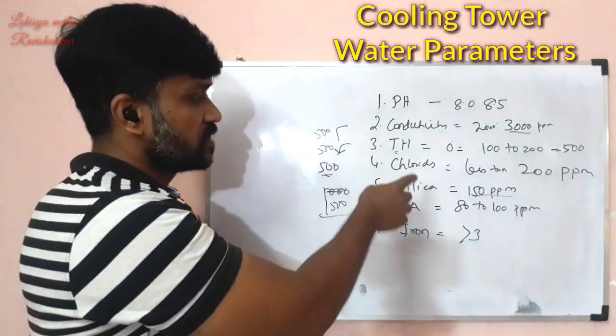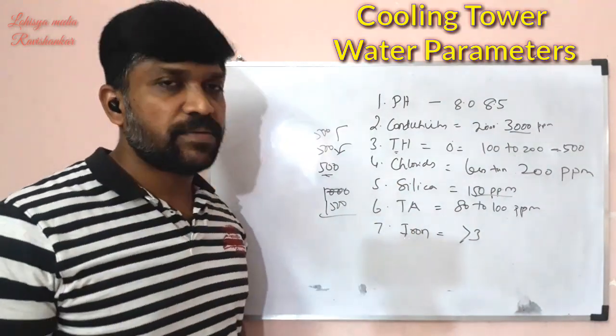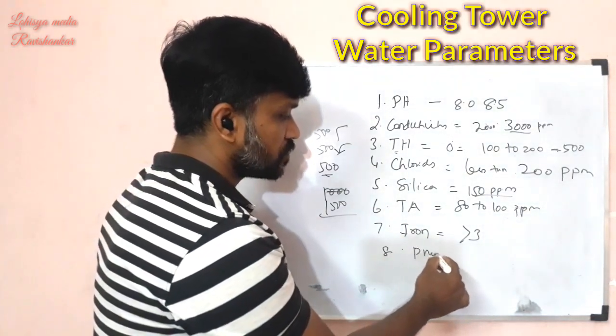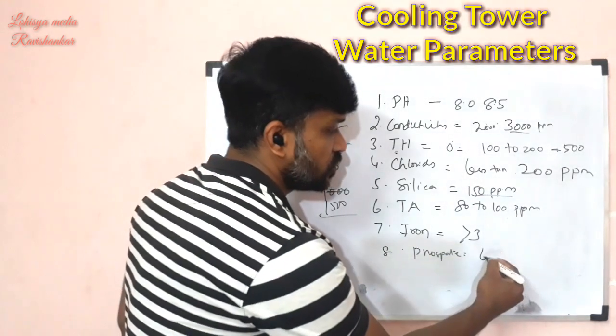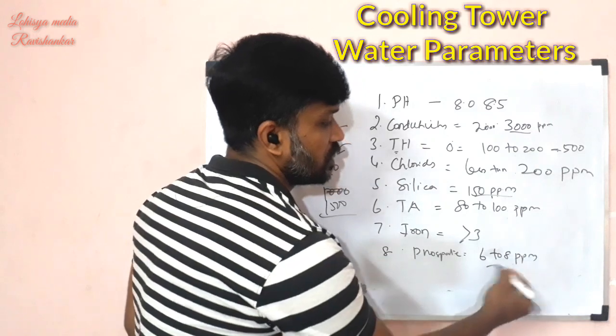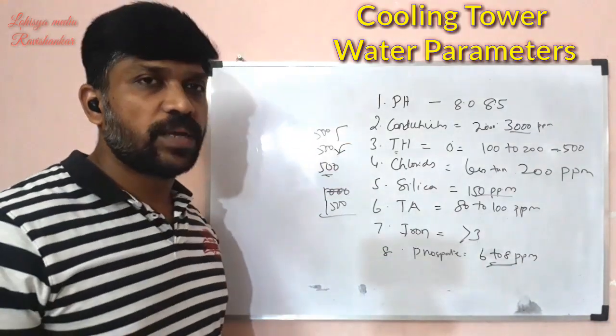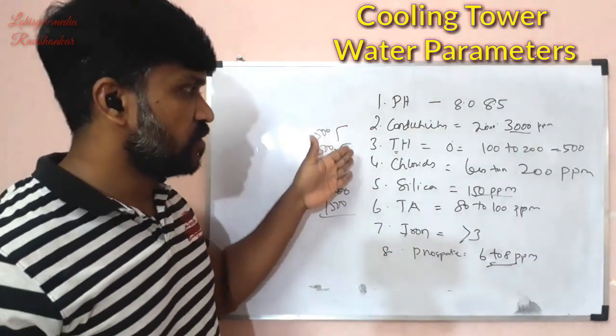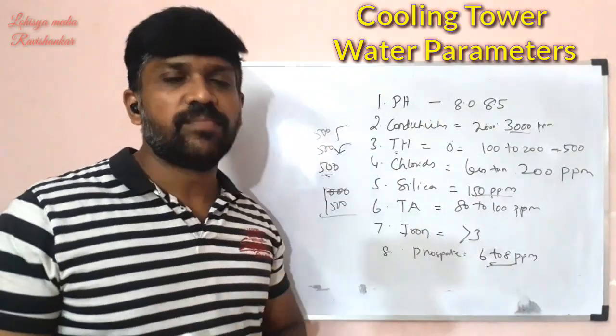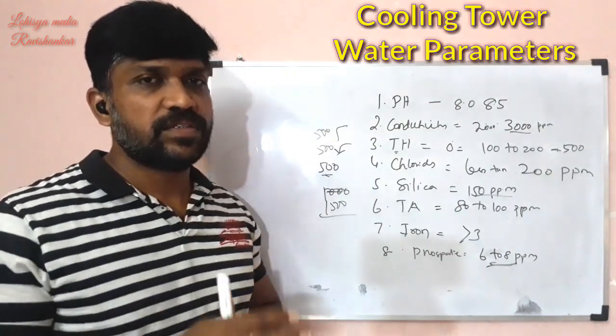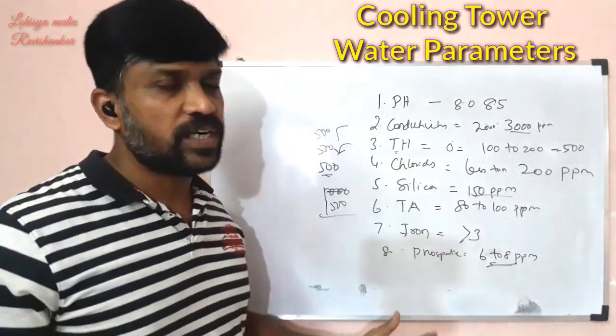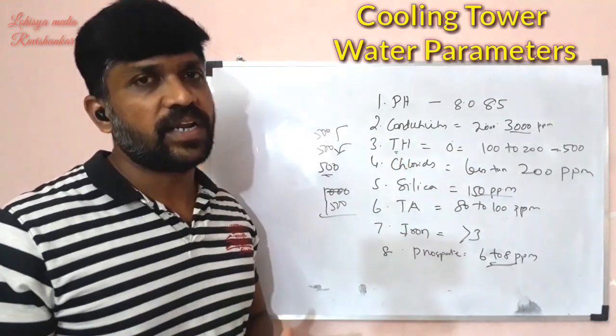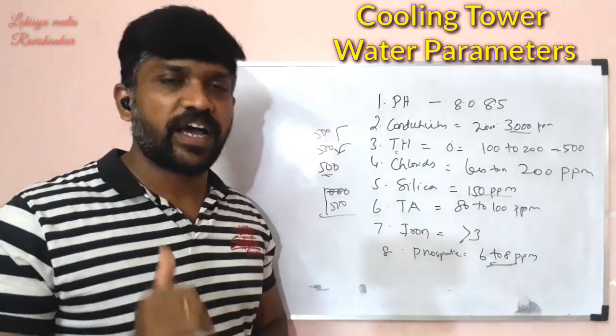If you check these parameters — pH, conductivity, total hardness, chlorides — and maintain them in range, the cooling tower will function properly. The pH should be in the range of 6 to 8. These values are important to maintain the cooling tower and check water quality. If these parameters change, the water quality will be affected, including biological values.